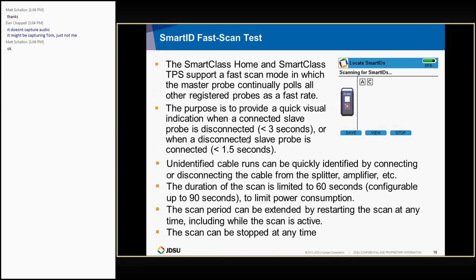So it's used to identify cable runs in a home, but because you're constantly pounding the network with polls and the remote probes are constantly generating responses, that tends to drain the battery at a faster than normal clip. So we limit the duration of the scan to 60 seconds by default, which you can raise to 90 seconds. And if a tech needs to extend the scan, he can push a soft key button. It'll restart the scan anytime, and he can stop it anytime he wants.